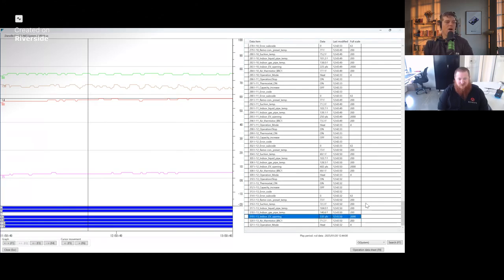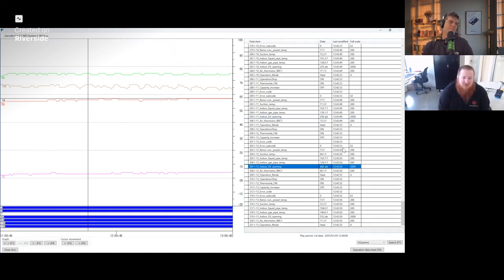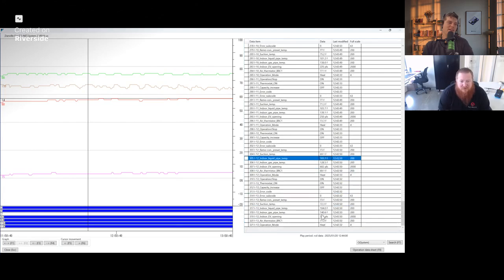Okay, so now here, looking at the indoor valve pulses, what would be your next thought process here, Donald, in looking at valve pulses? We're all low. It's low pulses. I'm seeing all those expansion valves that are like 315 to 500, and it looks like we've got decent coil heat. I'd be interested to see what the subcool is on our largest opening valve, what our subcooling value is. I love that.